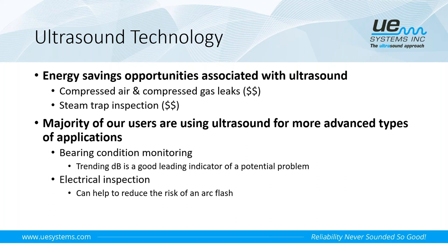And if we think about trending the decibel level, the unit of measurement for sound is the decibel, or dB. When we make contact with a bearing that is making noise, the Ultraprobe will show us the decibel level reading for that bearing. If we're trending that decibel level over time and it starts to increase, it means a change has taken place. So it's a really good leading indicator of a potential problem. And if we know the amount of increase in dB above the previous reading or above a baseline dB, we pretty well know what that problem is.